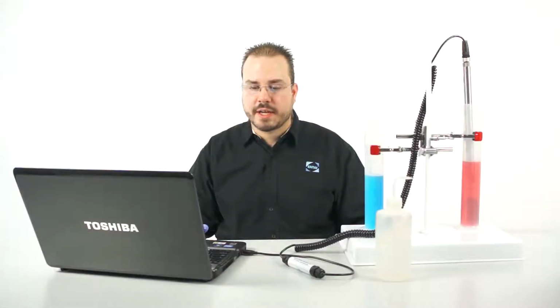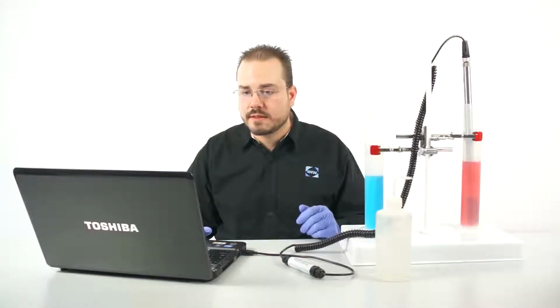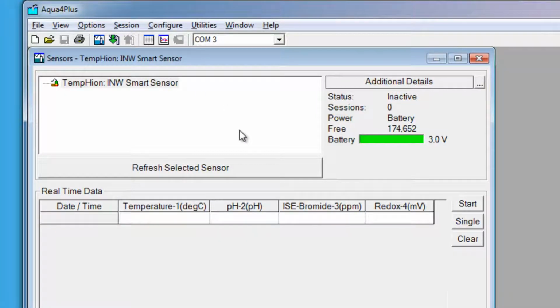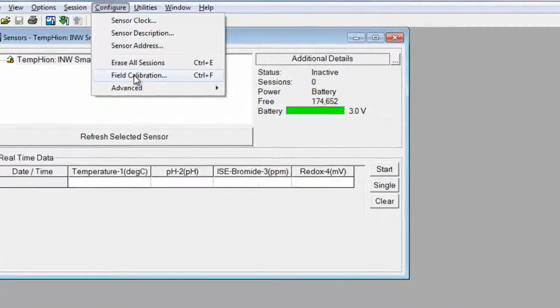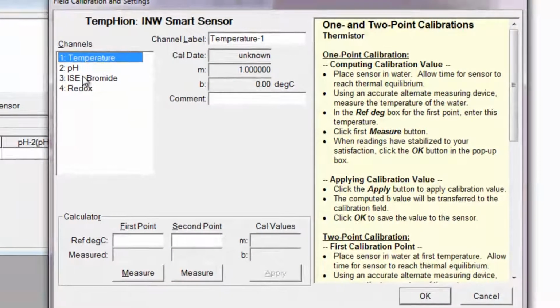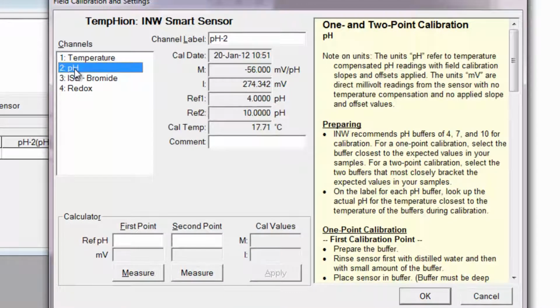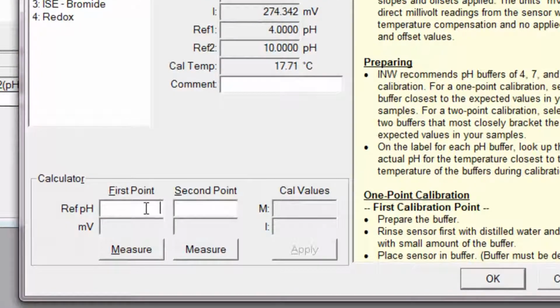I want to start by connecting the sensor to Aqua4 Plus. Once connected, you'll see the details all pop in on the window, and you'll know that you're ready to go to the Configure menu, Field Calibration. And since we're doing pH, we're going to select the pH channel. We'll then enter our first reference point, which in this case is pH 4.